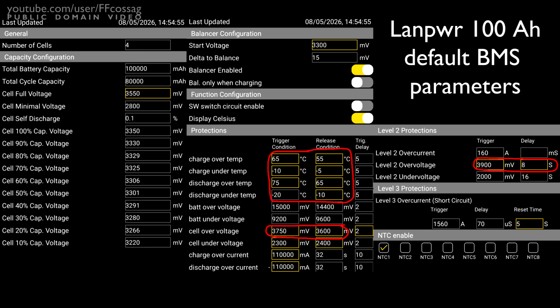So that is not good to see, but thankfully you can change the parameters. But Lanpwr, I urge you, provide some more sensible defaults. This is not good. The same goes for the cell under and over voltage thresholds. The over voltage threshold is 3.75 volts, which is too high for me. I would set that to 3.65. And the cell under voltage threshold is also fairly low at 2.3 volts, resetting at 2.4. I would set that to 2.5 and 2.6 volts.